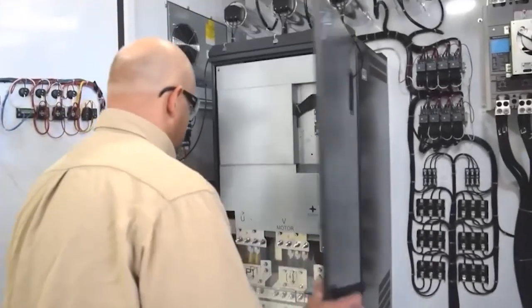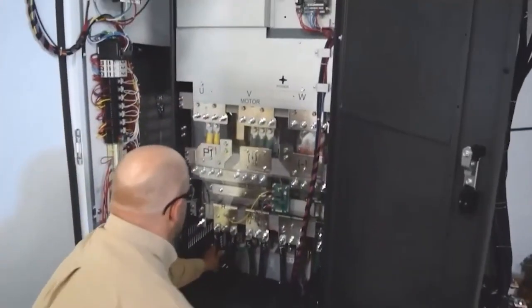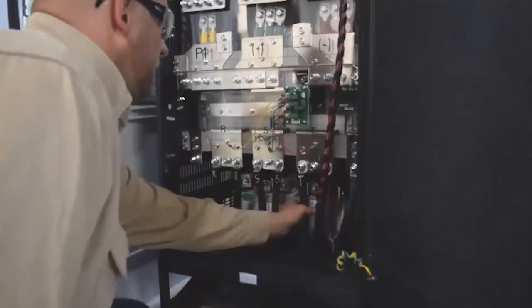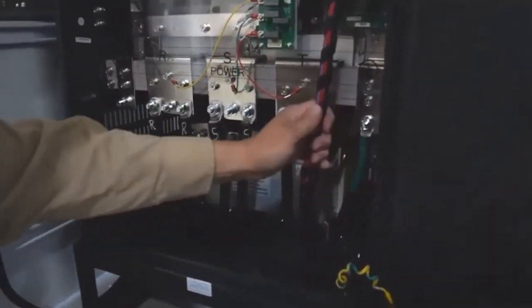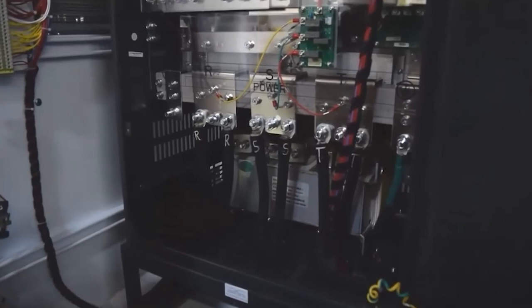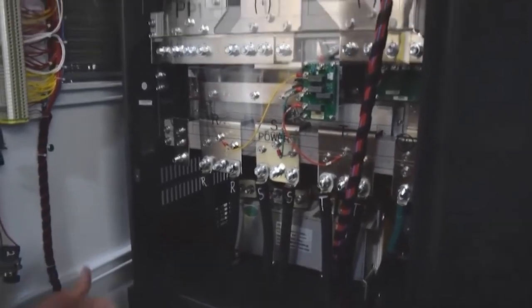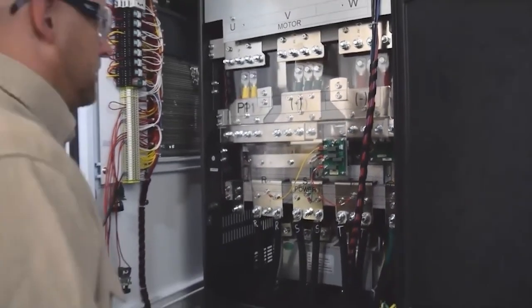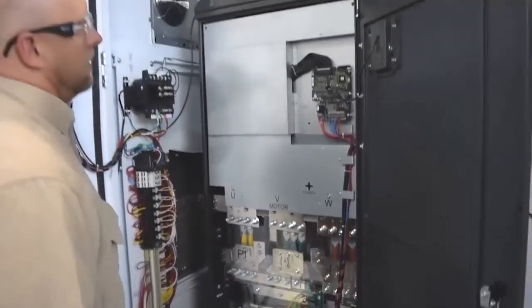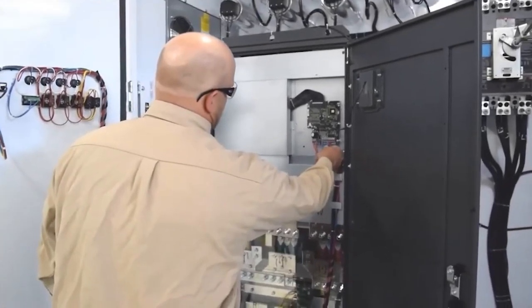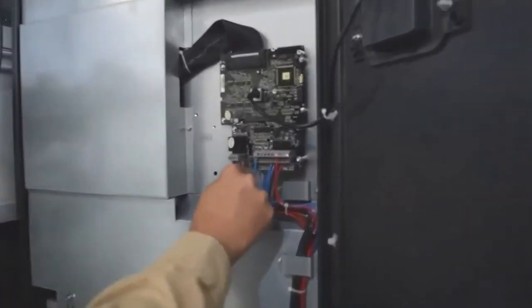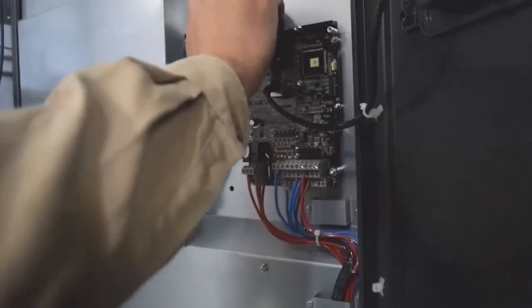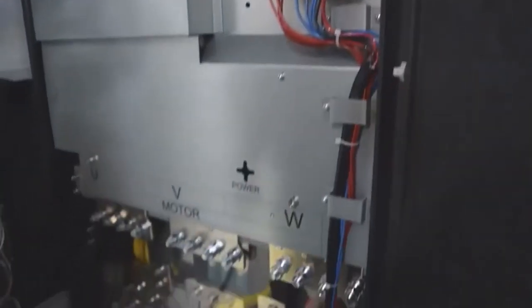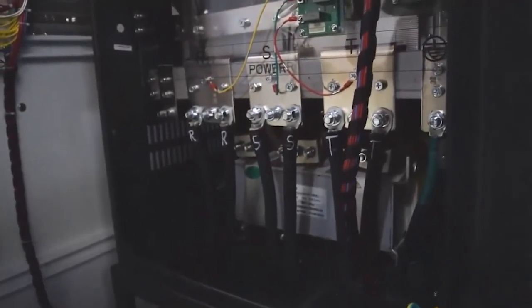All right, and we're going to open up the VFD cabinet. This one particularly has a door that opens up, which makes it a little easier. Sometimes you have to remove covers to get inside the cabinet, and we do a similar inspection. Make sure everything's tight. Make sure we don't have any bugs inside of it. Make sure we don't have anything inside that's not supposed to be there. Move on up, see the control board, make sure all the control connections look normal. Make sure all the ribbon cables are intact. Just give it a quick once over.